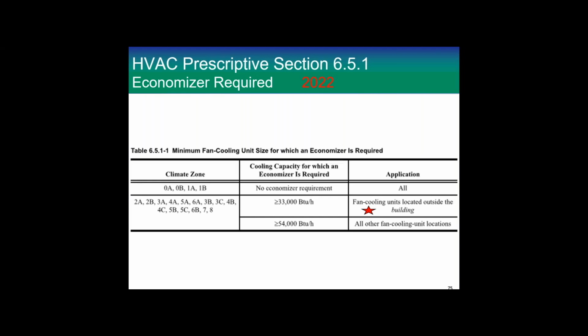And for 2022, we figured out that if a unit's outside, whether on the roof or sitting beside the building, it is cheaper to put an economizer in that unit. And so we have lowered the requirement to add an economizer to around 3 tons. If the unit's inside, where you have to duct and do some work for that economizer, then we're still at about 5 tons, 54,000 Btu/h, a little less than 5 tons. So that's new, lowering the threshold where you have to put in an economizer.